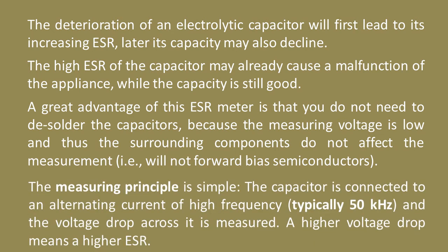The measuring principle is simple. The capacitor is connected to an alternating current of high frequency, typically 50 kHz, and the voltage drop across it is measured. A higher voltage drop means a higher ESR.